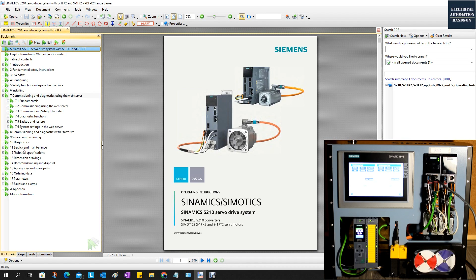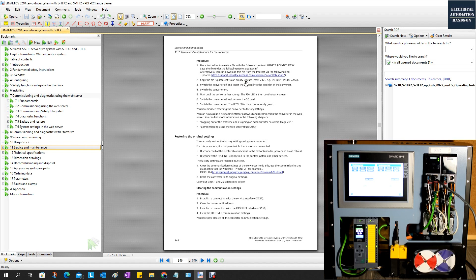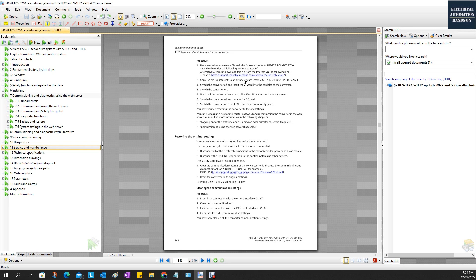To reset this servo drive's password to the initial state, you have to use one empty SD card—this is the Siemens SD card. You have to use one empty SD card to reset this servo drive. So if you really forget this password, that will be really annoying, so make sure you write down this password somewhere.